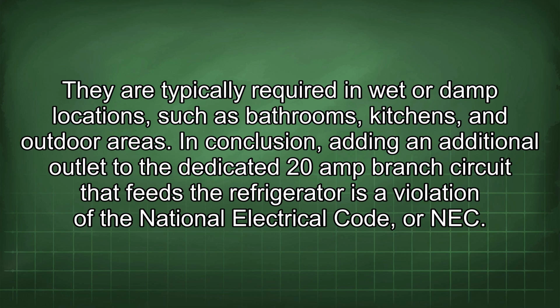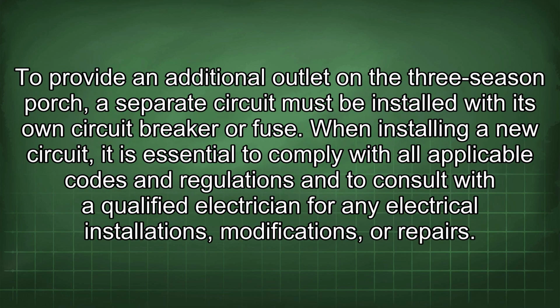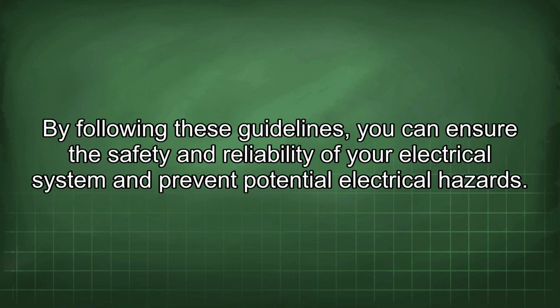In conclusion, adding an additional outlet to the dedicated 20 amp branch circuit that feeds the refrigerator is a violation of the National Electrical Code, NEC. To provide an additional outlet on the 3-season porch, a separate circuit must be installed with its own circuit breaker or fuse. When installing a new circuit, it is essential to comply with all applicable codes and regulations and to consult with a qualified electrician for any electrical installations, modifications, or repairs. By following these guidelines, you can ensure the safety and reliability of your electrical system and prevent potential electrical hazards.